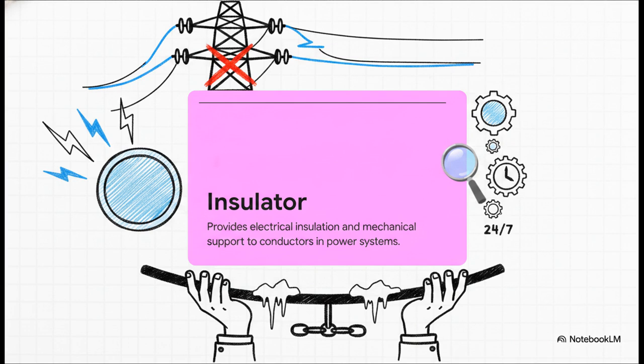They don't just stop electricity from taking a shortcut down the pole and into the ground, they physically hold the entire grid together. Think about it: those conductor lines carry immense weight, especially over long distances or when coated in heavy winter ice. If an insulator fails mechanically, the line physically drops to the ground. If it fails electrically, the power just shorts out. It literally has to perfectly execute both of these intense jobs simultaneously, 24/7, no days off.